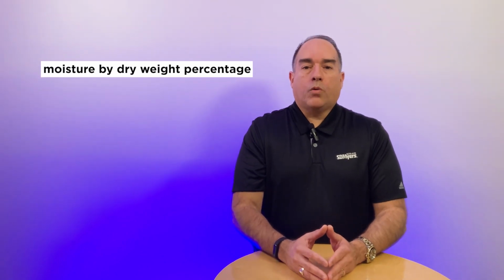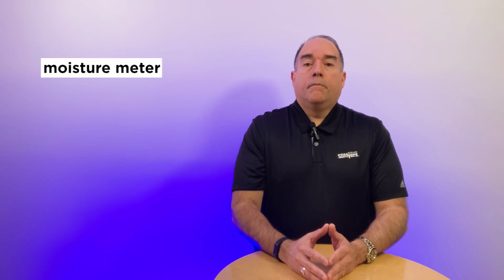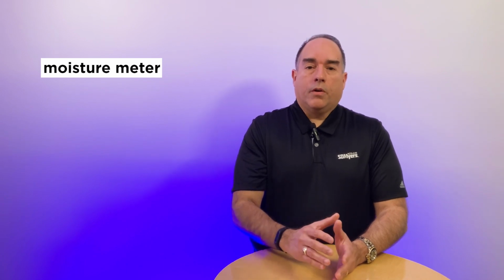Additionally, SDMyers can calculate the moisture by dry weight percentage, which gives an estimated amount of moisture in the solid insulation compared to the oil. Another way to test moisture in the transformer is with a sensor called a moisture meter. These sensors can be installed on the transformer or are in oil processing rigs that they read temperature and percentage of saturation. Water content can then be calculated from those.